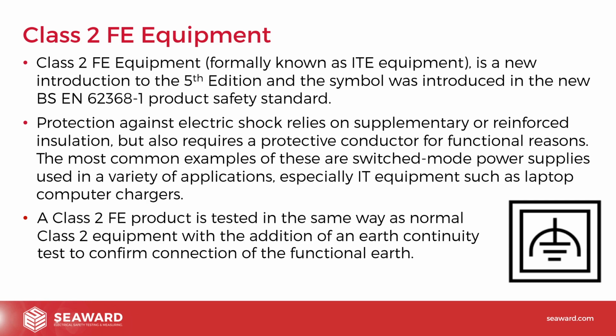One bit I just want to mention in here because it's important: the actual pass-fail limit. All we're checking is for continuity. Is it continuous? Is it relatively low resistance? There is no specific pass-fail value for this, although the equipment manufacturer may be able to provide you with typical values or values that they would expect to see on their particular equipment. So the 0.1 plus R, the normal earth continuity limit, doesn't apply for this because it's not designed for protective earthing. So it may have a higher earth reading or resistance reading than you would normally expect on normal equipment.